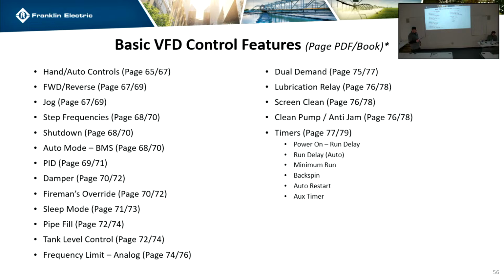Yep, so it's just a basic setup. Your auto speed ref, for what you guys are going to do, is going to be the TV or TC. If you do get into a PID loop, it's also on this page, and you would basically go through, set your auto speed ref to say PID output, your auto run command, it could be digital input or keypad, it doesn't matter. You would go into PID mode, which is set 17, and turn it on. And then once you turn it on, you go into the next ones, the 18, 19, 20. You just go through the whole thing.